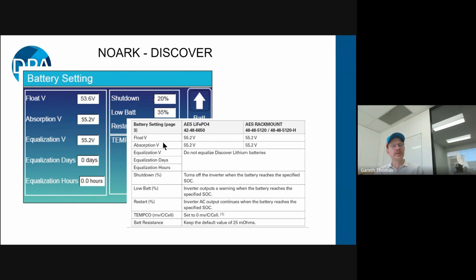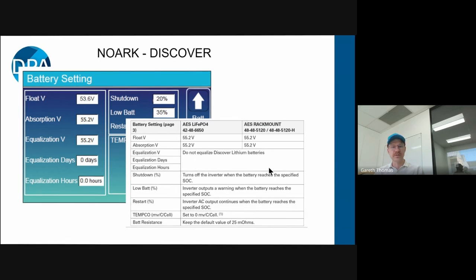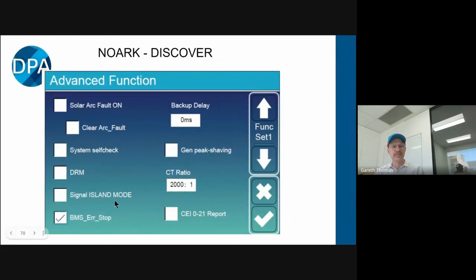If you were doing open loop, you would put in all these charge settings - you can see there's an excerpt here from the manual - just like you would with lead acid. You want to have this enabled in the advanced function menu in NOARK, which is the BMS error stop. What that means is if you don't have that enabled, there's a chance the inverter will keep doing whatever the last command from the battery was. If the battery loses communications, that's a NOARK thing - other inverters behave differently. You want the inverter to shut down when it loses communications, so that's what you have here.